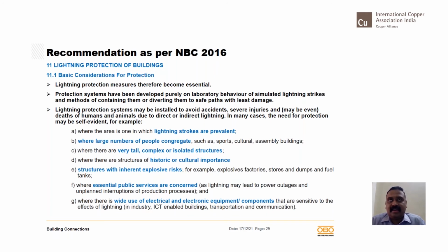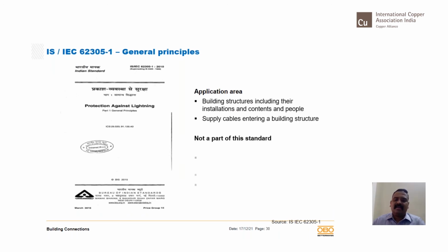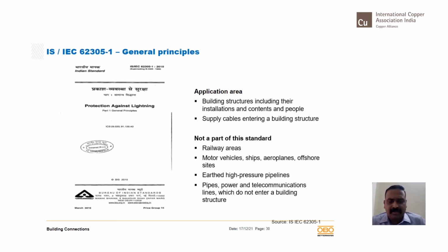So with these categories, almost every kind of building falls under this. So there is no question of whether my building requires protection. There is no question at all. Any building that has basic amenities which are to be protected against failure and against damage requires lightning protection. The substantiating standard, the IS standard, is adopted in toto from IEC 62305. It has 4 parts, which basically give a complete explanation of the do's and don'ts, the maintenance aspect and everything about lightning protection. Part 1 talks about general principles.